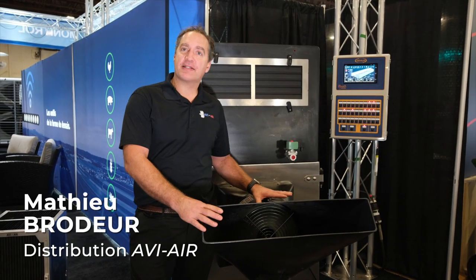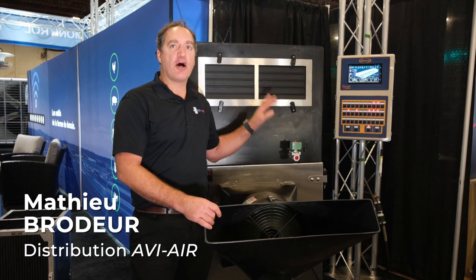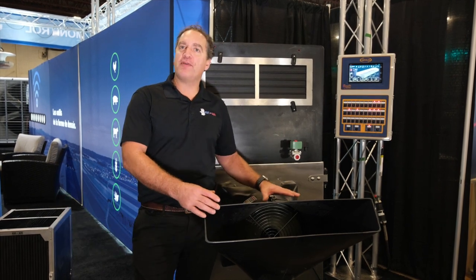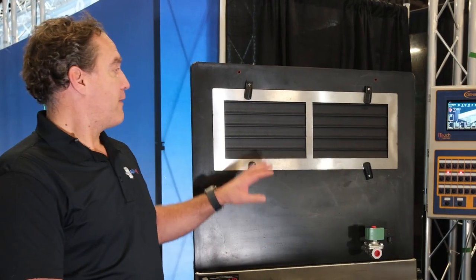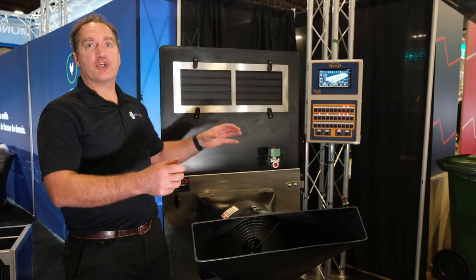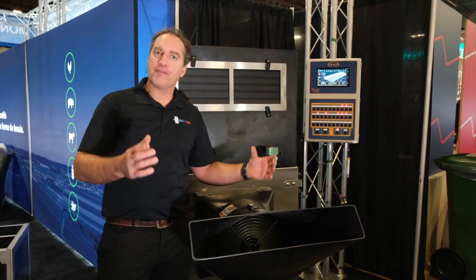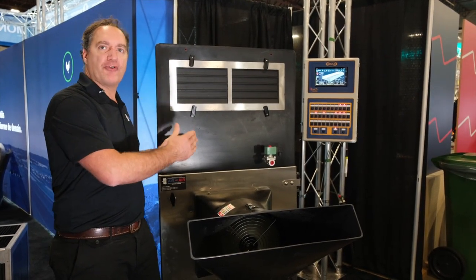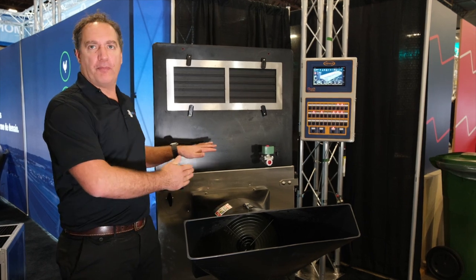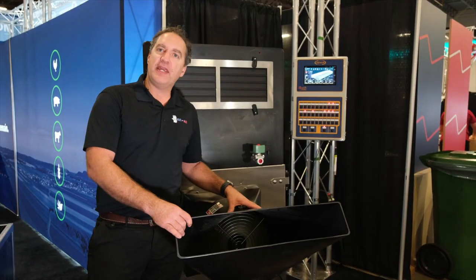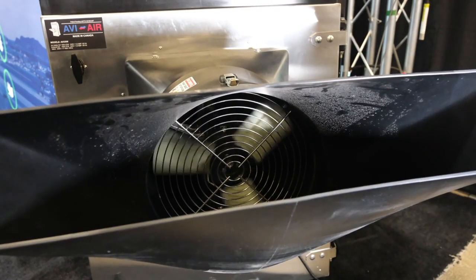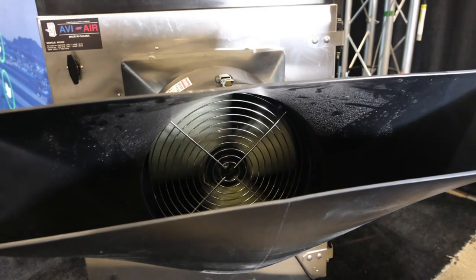This is a dual fan system, heat exchanger, exhaust and intake fan to recover the heat from your farm building. We have the exhaust fan up here, which sucks in the moist air from your building. The moist air goes through channels inside the heating core, out your building. As the heating core is getting warmed up, the incoming fresh air goes through the core in different channels and then is being propelled and pushed inside your building via the intake fan. So it's a dual fan system that recovers heat from your building.